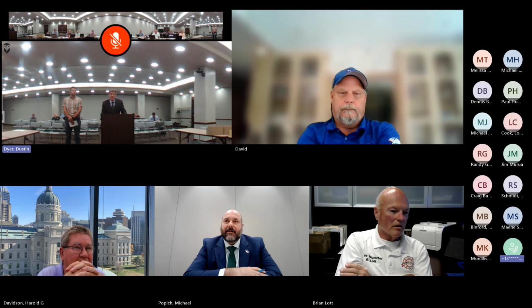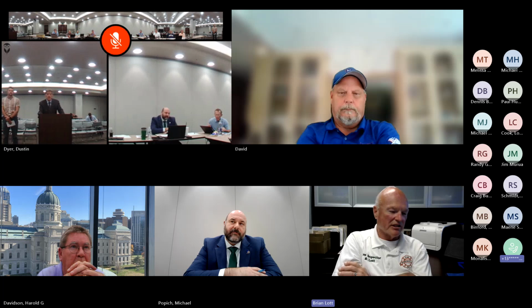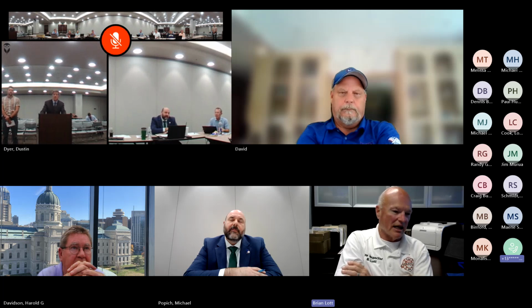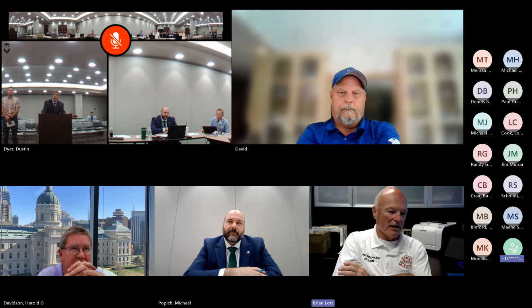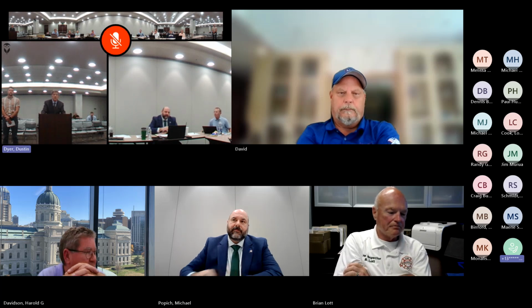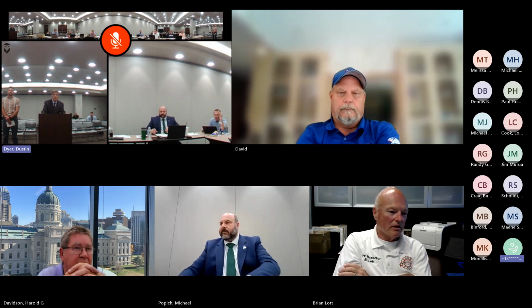We have quick response sprinklers on 40% of these. That makes no sense. The decks are fine, but it's the 59, the number that they had the standard response heads on the balconies that need to be fixed. So they need to replace 59 heads, have to go to quick response.